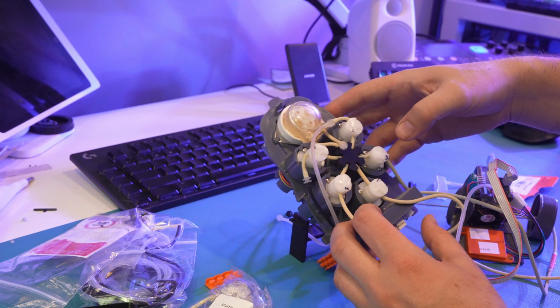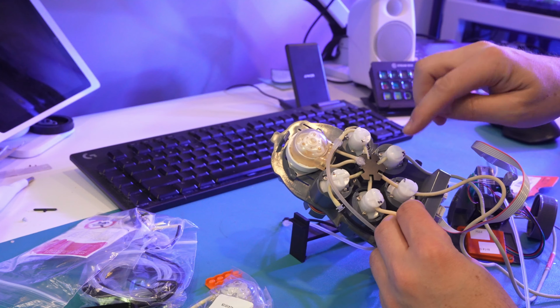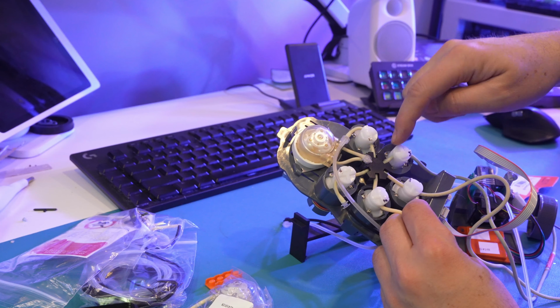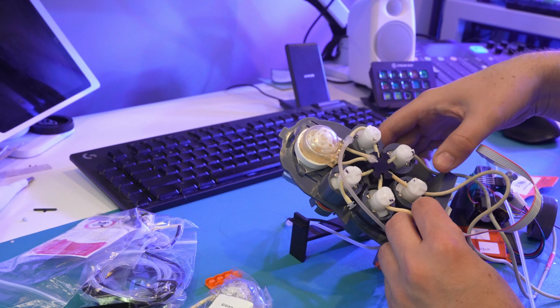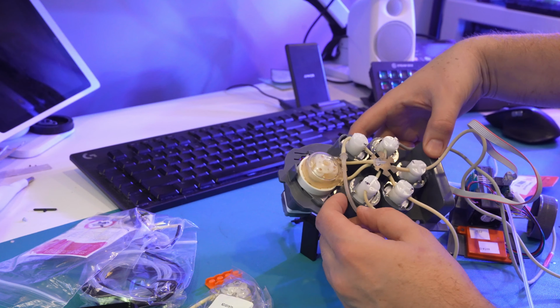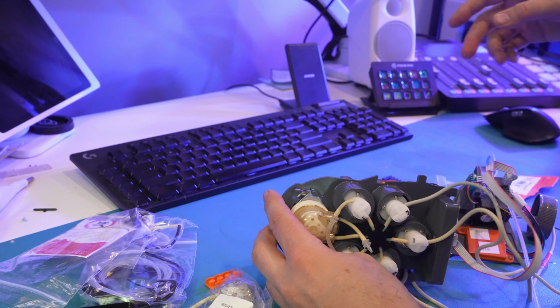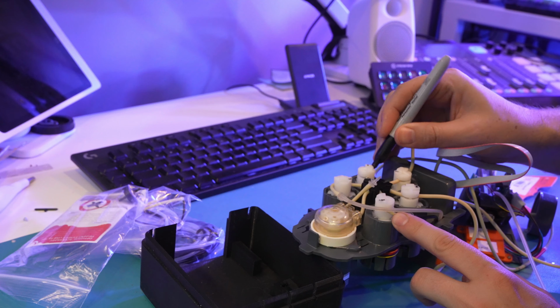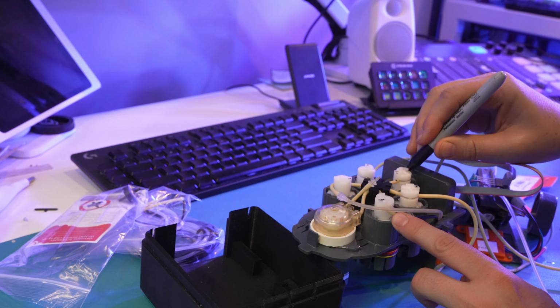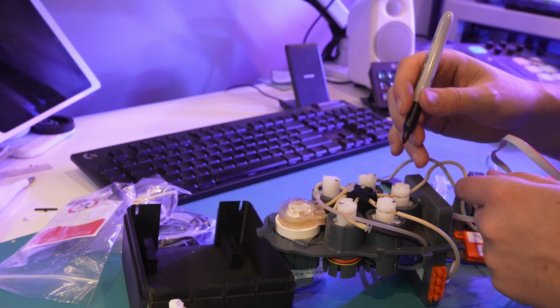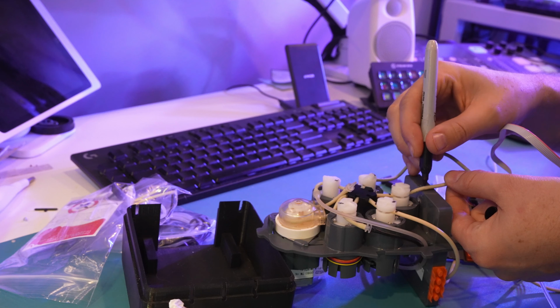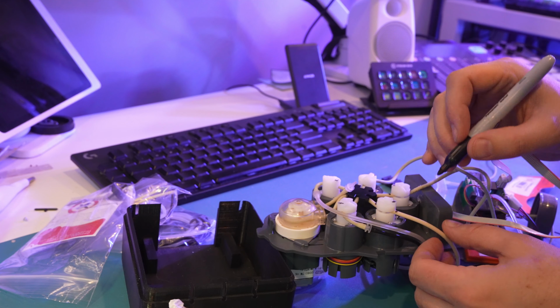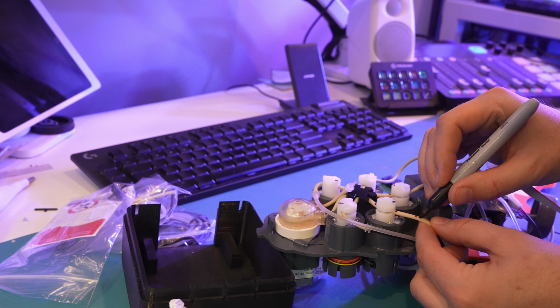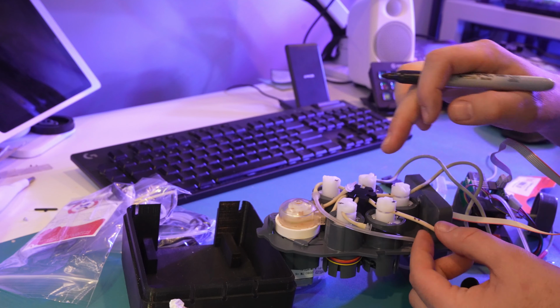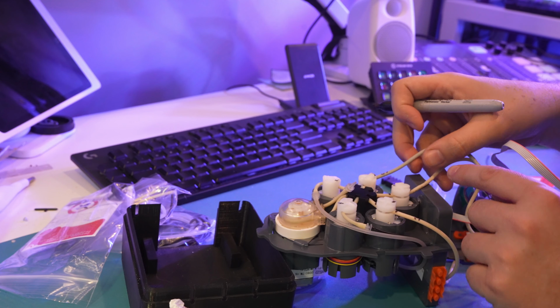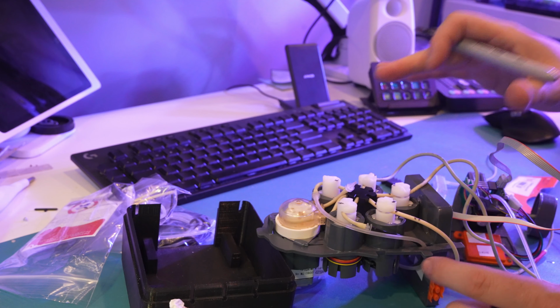Now, if you watch the original videos, Paul does recommend you make some marks on either side of this tubing of where it connects. So we're going to do that just so we can put the reagent lines back into the proper spots. And we're just going to put a little tiny mark on either side of it. And this is just going to be for lining it back up. I am going to go one further and actually just write on what they are. So there's a 1. So we got 1, 2, 3, 4, 5. So I just did 2, 1, and 5 just so it's really easy to know which ones go where for later.